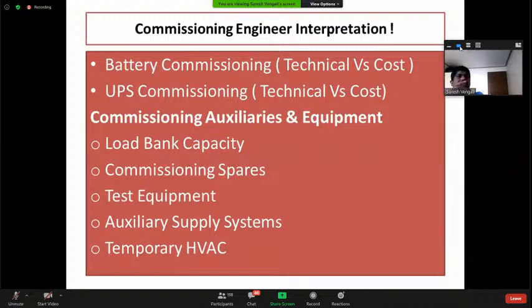Proving it means you need many auxiliary supplies. If we forget this auxiliary supply information during the commissioning phase, it impacts the project cost, like your load bank capacity. Suppose you're bringing a 160 amp hour battery or 1000 amp hour battery, you need the load bank sized accordingly. If the load bank is not specified properly, you bear the cost.